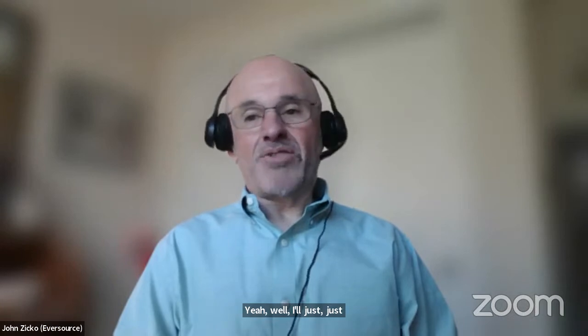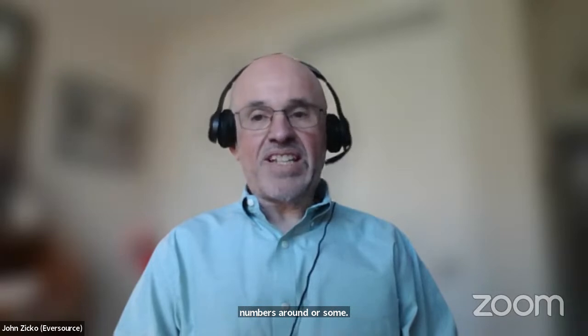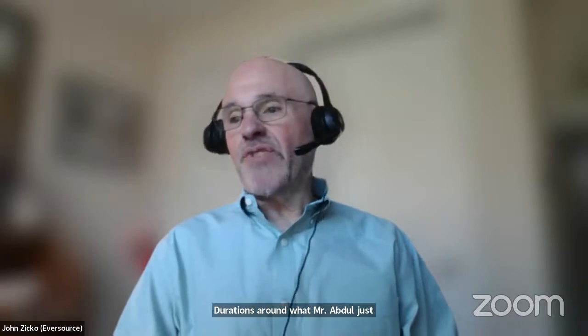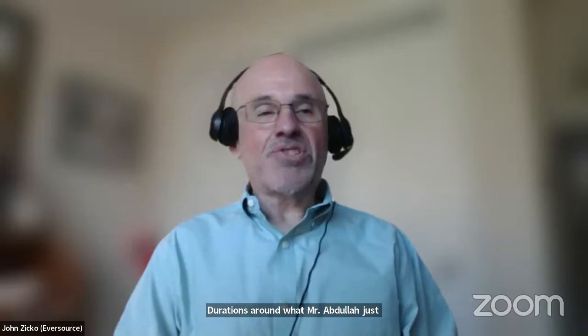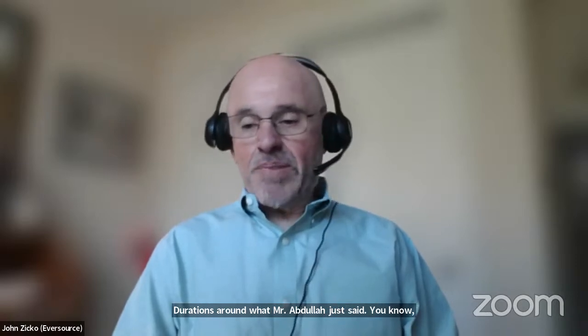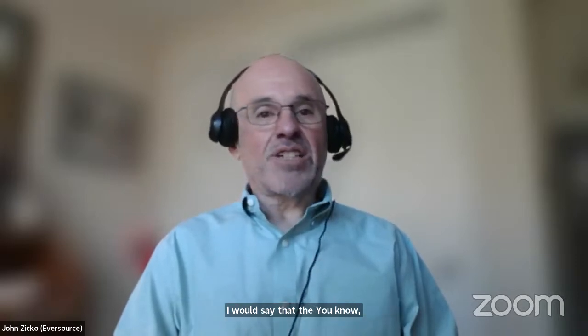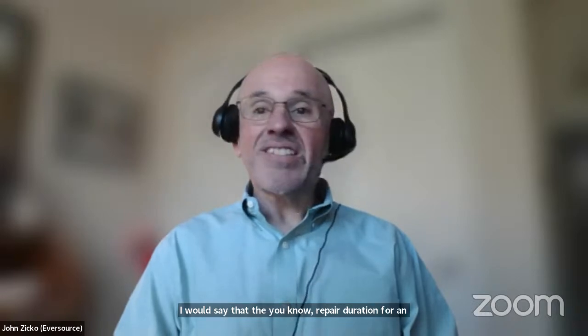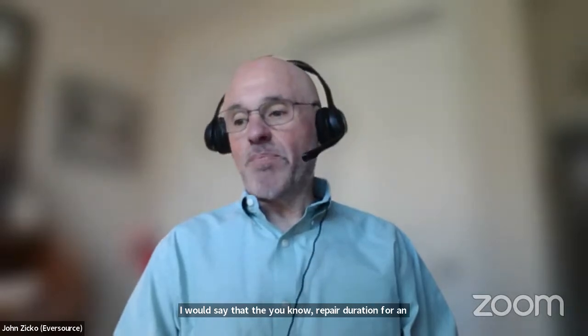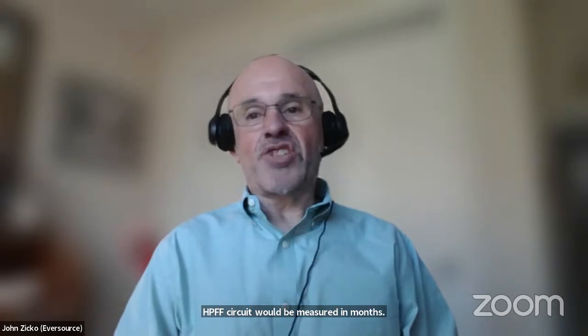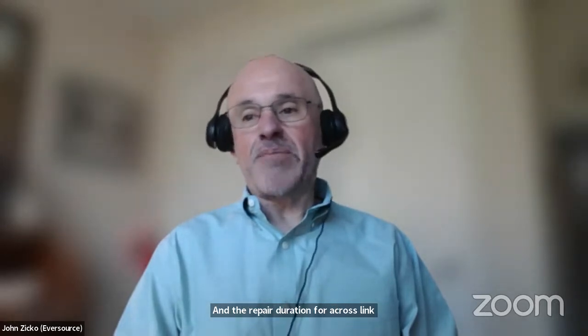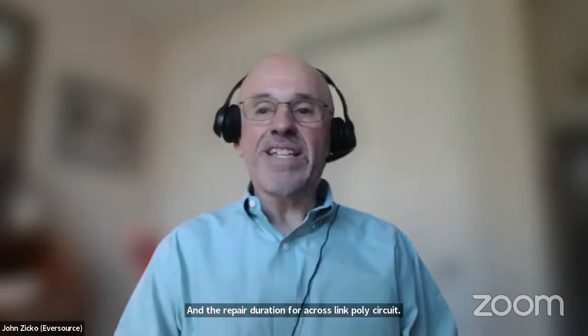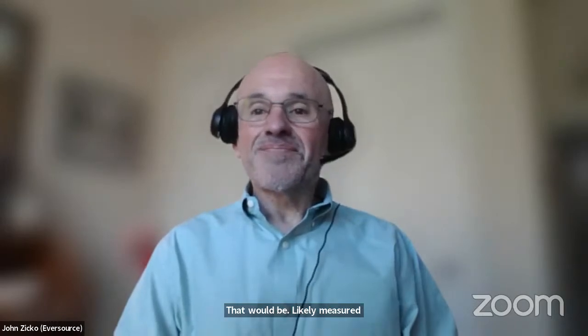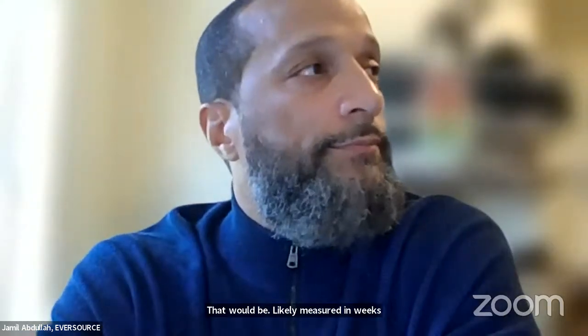I'll just put some durations around what Mr. Abdullah just said. If I were to characterize it, I would say that the repair duration for an HPFF circuit would be measured in months, and the repair duration for a cross-link poly circuit would likely be measured in weeks. Thank you. That was really helpful.